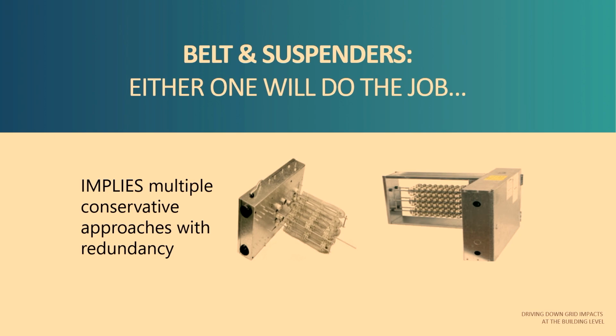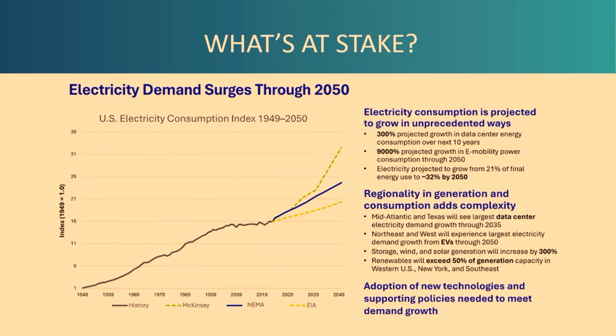That one decision matters. What if somebody goes in and, belt and suspenders, says, I want a 15 or 20 kW backup heat on that 2-ton heat pump? Does that really make sense? Number one, no. It just does not. So we have to be reasonable. We have to be respectful for what we're doing.